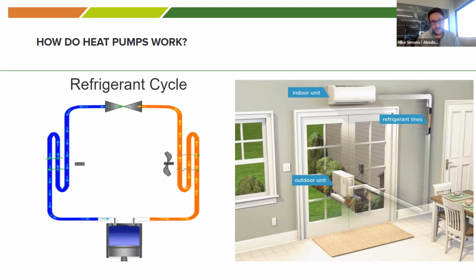Heat pumps work the exact same way. So let's just say hypothetically, it's 0 degrees outside. 0 degrees is very cold, but it's not nearly as cold as -30 degrees. So that tells me that even at 0 degrees, there's a lot of energy in the outside air because it's warmer than -30 degrees. So how a heat pump is going to work is it's going to take refrigerant that could be -30 degrees and bring that refrigerant outside. -30 is colder than 0, and hot goes to cold. So that 0 degree air is going to pass over this -30 degree refrigerant until the refrigerant's no longer -30, but it's going to warm up. It's going to be -2 degrees or -4 degrees.